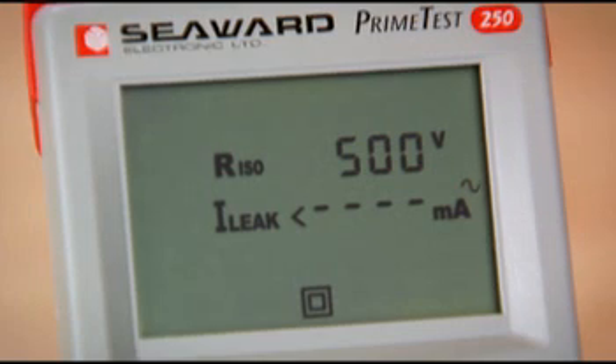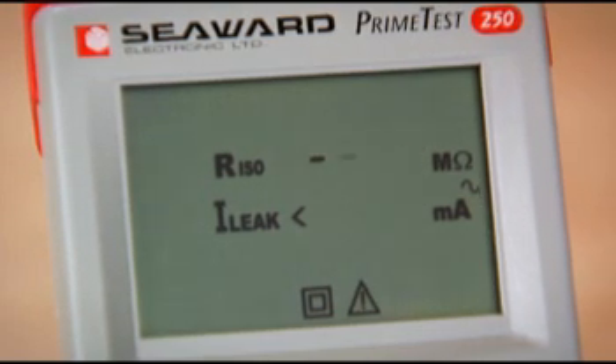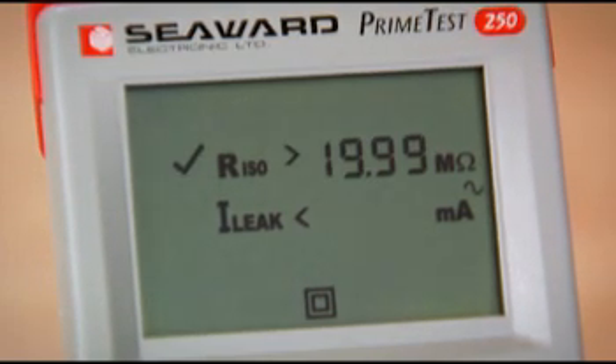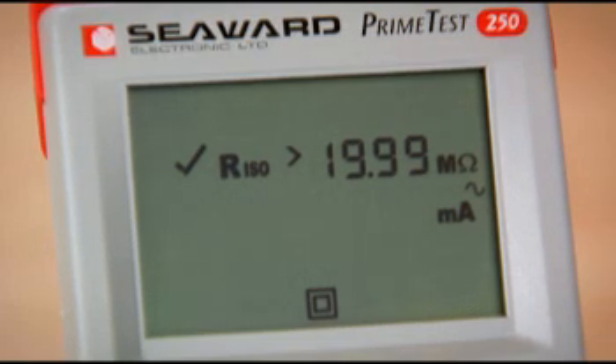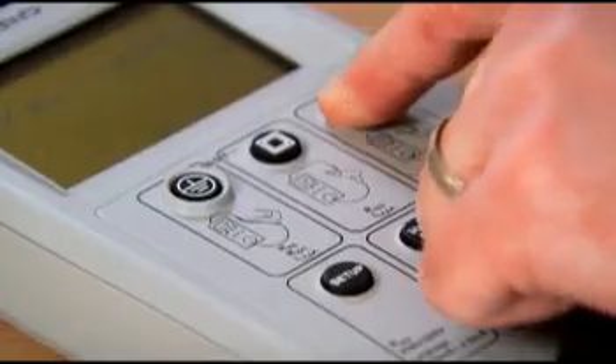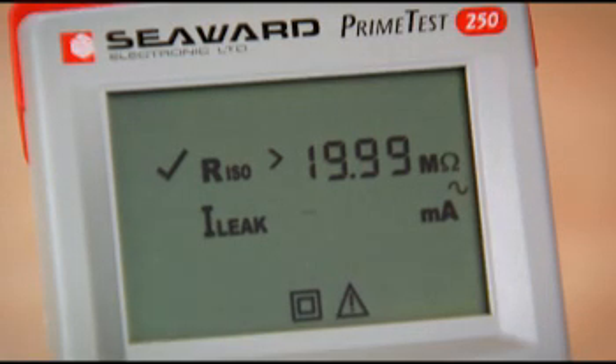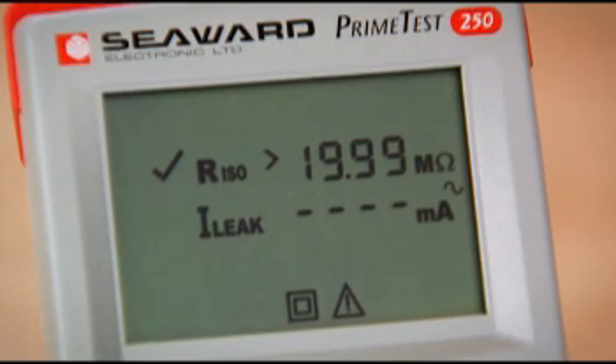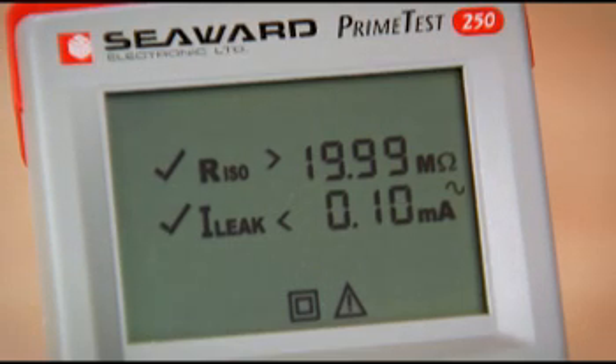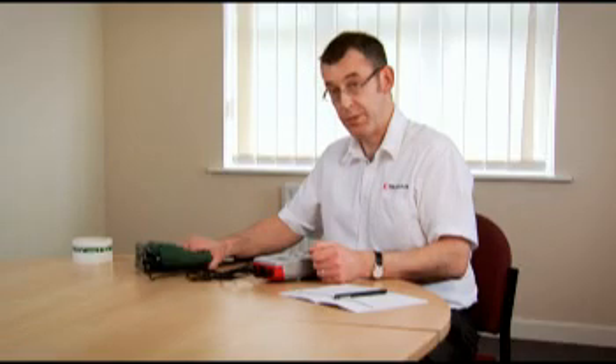First off, it measures the insulation, and now it's going to power the appliance. It's ready to do so, so it's flashing the leakage key. I press this button to confirm it's safe to proceed. Pressing the button a second time terminates the test, and the sequence is now complete.